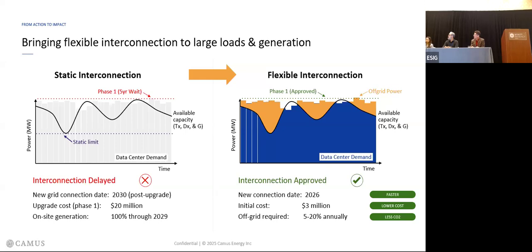What they did was put sensors to look at the impact of that fleet load on the grid around it, and had an agreement with the fleet to stay below a certain cap over a certain period while the upgrade was put in place—kind of a bridge to wires model. What they found was that they actually didn't really need to do the upgrade as planned. When they could monitor it, and the site could provide a certain amount of curtailment, they ended up getting away with about a $400,000 upgrade instead.